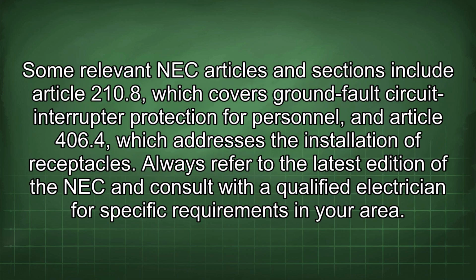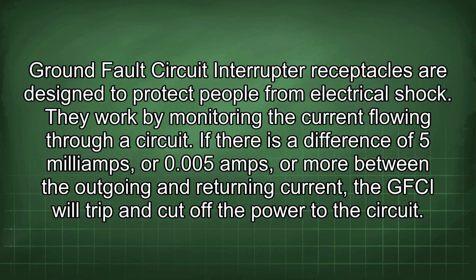Some relevant NEC articles and sections include Article 210.8, which covers ground fault circuit interrupter protection for personnel, and Article 406.4, which addresses the installation of receptacles. Always refer to the latest edition of the NEC and consult with a qualified electrician for specific requirements in your area. Ground fault circuit interrupter receptacles are designed to protect people from electrical shock. They work by monitoring the current flowing through a circuit. If there is a difference of 5 mA or 0.005 amps or more between the outgoing and returning current, the GFCI will trip and cut off the power to the circuit.